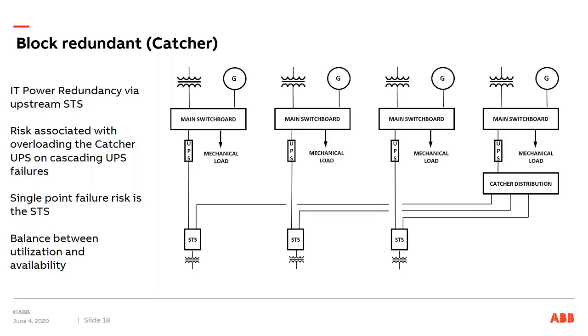So this just shows 4 UPSs. I've seen catcher systems with up to 8 or 9 UPSs with 1 catcher. And of course, you don't gain as much. If you had 5 UPSs instead of 4 in this one, you would have 4 main UPSs and 1 catcher. That would bump the utilization up only from 75 to 80%. But of course, it still matters. So going to 6, 7, and 8 still improves utilization, but it's diminishing percentage-wise. So this is one popular design we see for large data centers now.